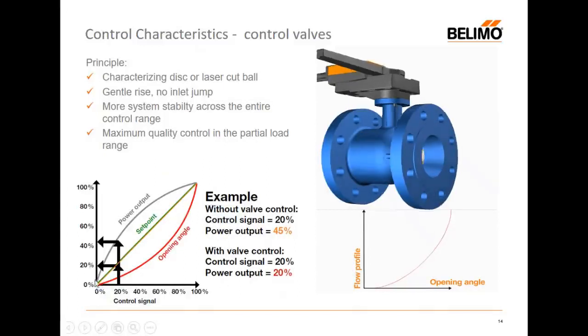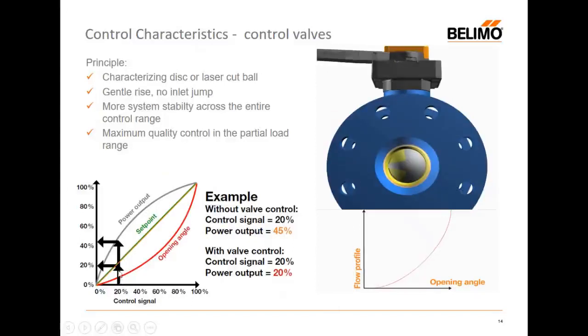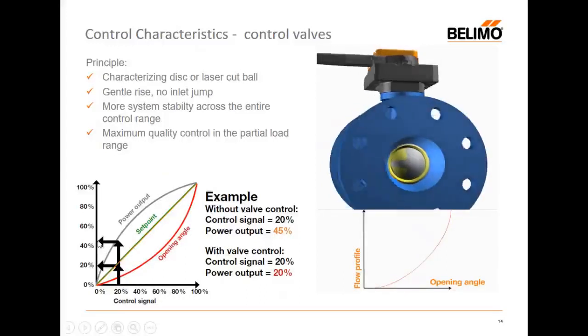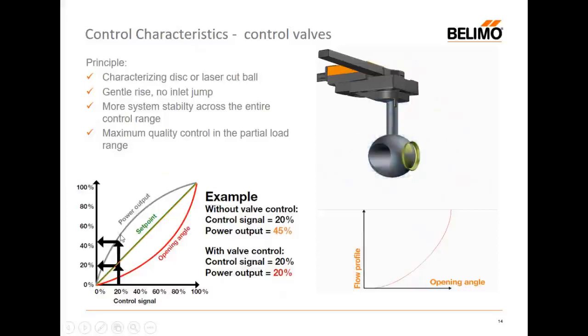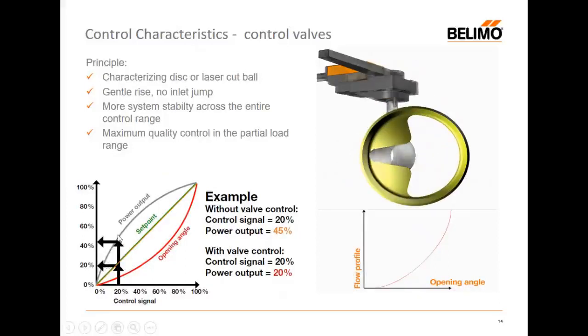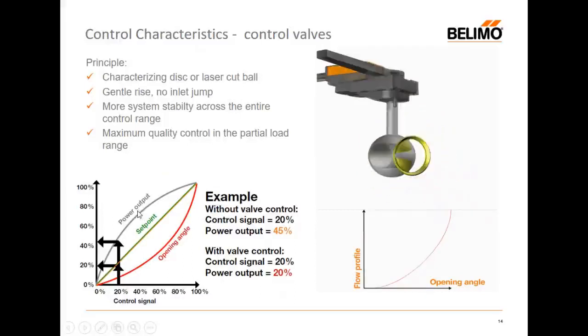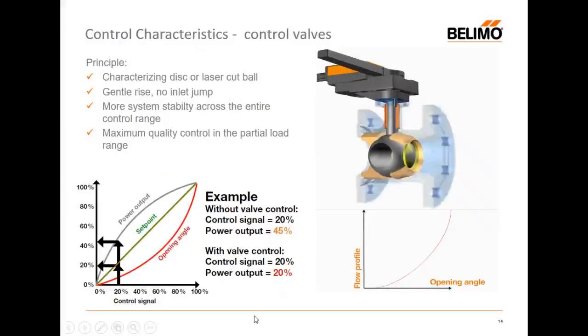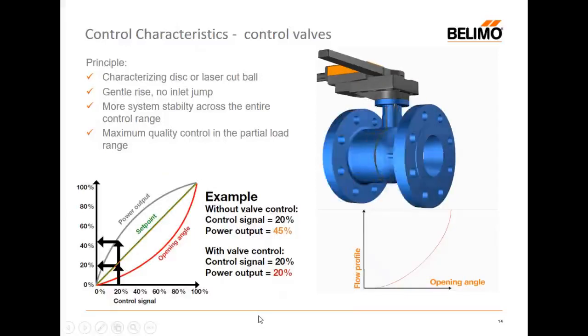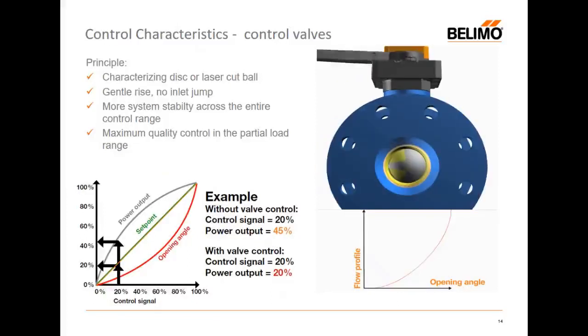If I'm not on an EQM valve and I'm controlling without an EQM valve, then I could be giving a 20% opening or a 2-volt signal and end up with 45% of the power, and it's not stable. And in light load, which is where most systems live, this instability, this very small movement for a very big power output is not required. It really will mean that we'll overflow and underflow circuits very easily. Valves will hunt, they will overflow and saturate coils far too easily, and it's not desirable.